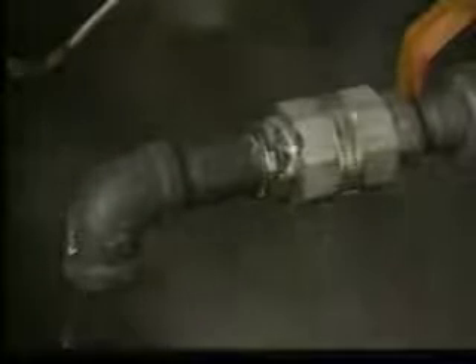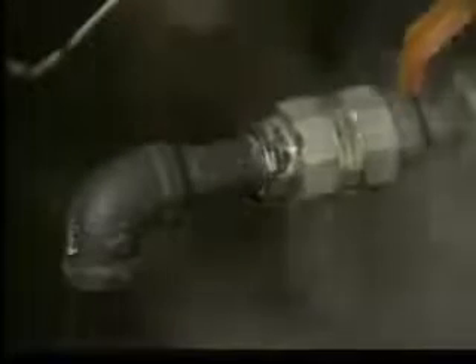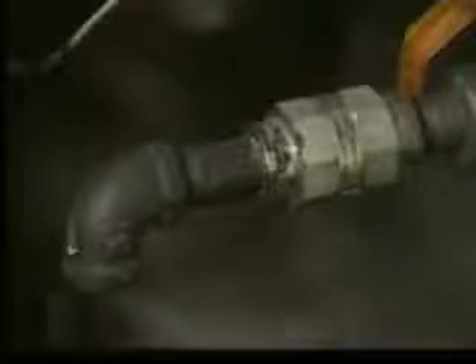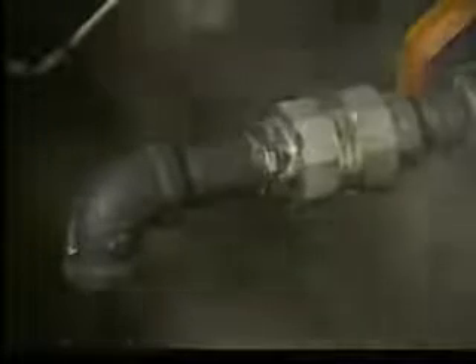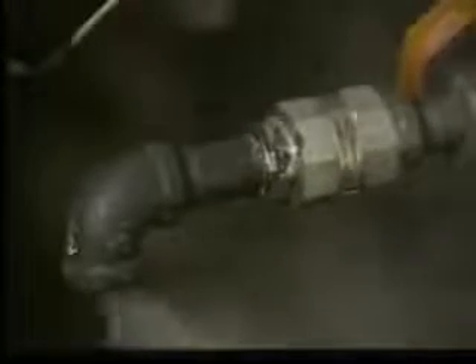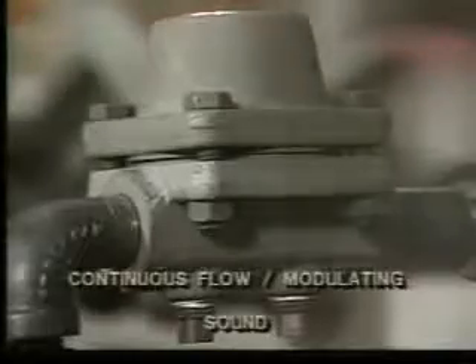There are two major types of steam traps, intermittent and continuous flow. Intermittent traps have a normal hold, discharge, hold pattern. Continuous flow traps produce a steady, modulating sound.